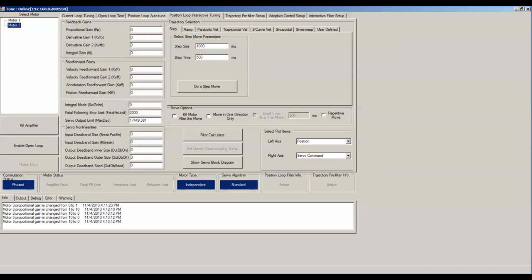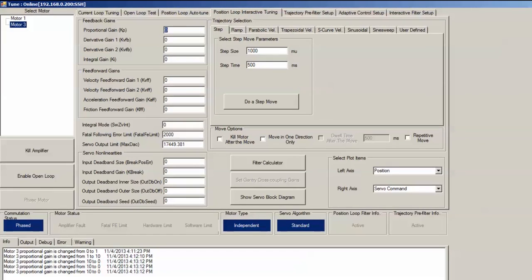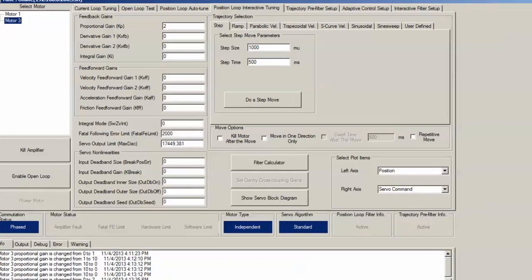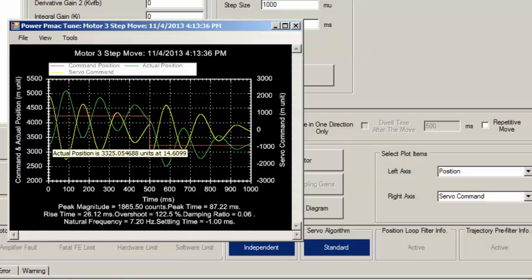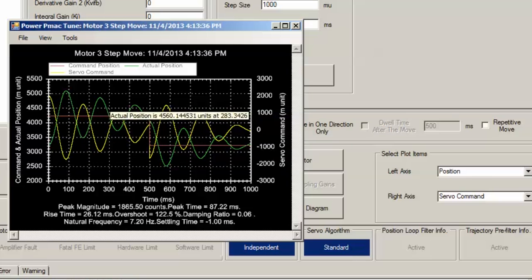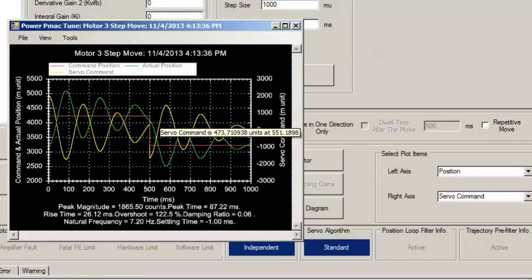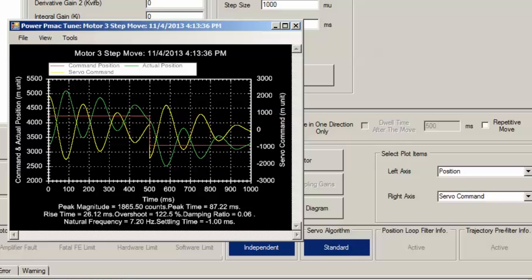Since I know from experience that a motor this size takes proportional gain values between 0 and 100, I'll start with a pretty conservative value of 2, and we can do a step move and see where we are. We can see that the motor actual position in green is overshooting and oscillating the commanded position in red just like we wanted, but the natural frequency is quite poor.